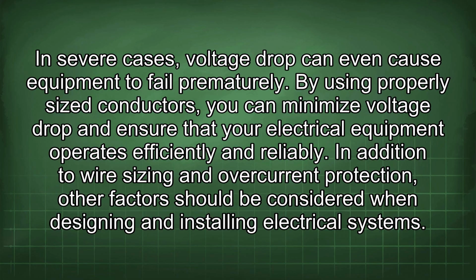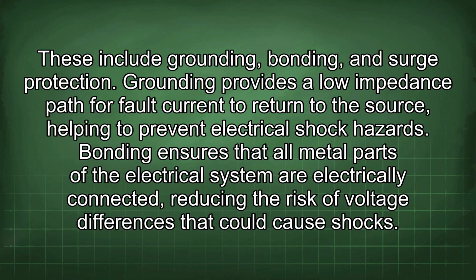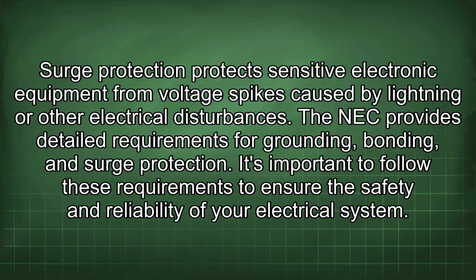In addition to wire sizing and overcurrent protection, other factors should be considered when designing and installing electrical systems. These include grounding, bonding, and surge protection. Grounding provides a low impedance path for fault current to return to the source, helping to prevent electrical shock hazards. Bonding ensures that all metal parts of the electrical system are electrically connected, reducing the risk of voltage differences that could cause shocks. Surge protection protects sensitive electronic equipment from voltage spikes caused by lightning or other electrical disturbances.